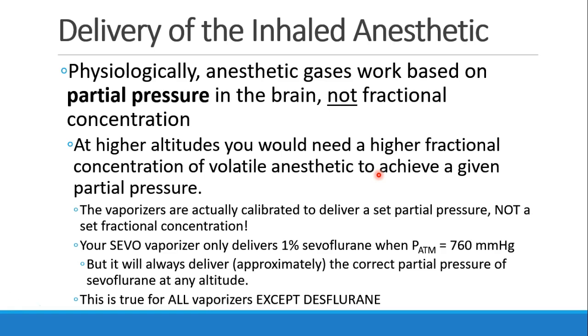The patient's still getting 1% isoflurane, but 1% of what? A very thin air. And it's not the 1% that the brain needs to have anesthesia — it's the 7.6 millimeters of mercury. And our vaporizers are actually calibrated to deliver a partial pressure, not a fractional concentration. Even though the dial says 1%, it's really calibrated to deliver a partial pressure. So your SEVO vaporizer actually only delivers 1% when you're at atmospheric pressure of 760 at sea level, but it will always deliver approximately the right partial pressure at any altitude. And this is true for all of our vaporizers except desflurane.